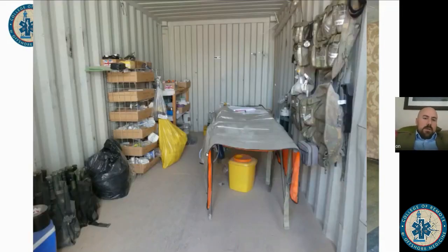But again, other makeshift ideas for your level 1 intensive care can be in the back of an ISO container. Either battery powered non-invasive monitoring or something that's connected to a power supply are all things you need to think about. And if it's batteries, then your facility is only as good as until the batteries run out. So you need a way of charging that.